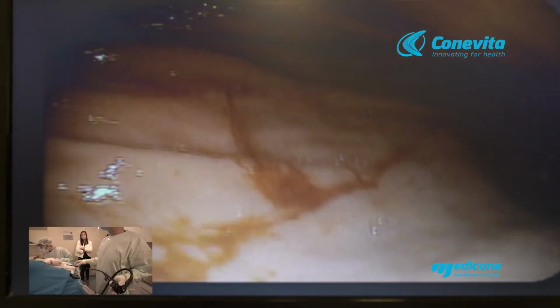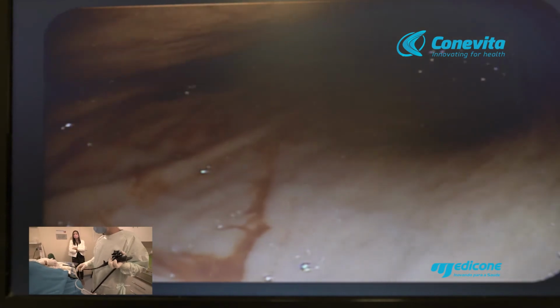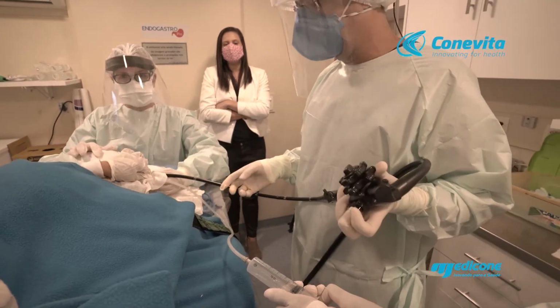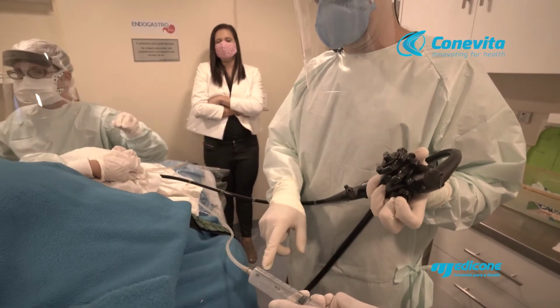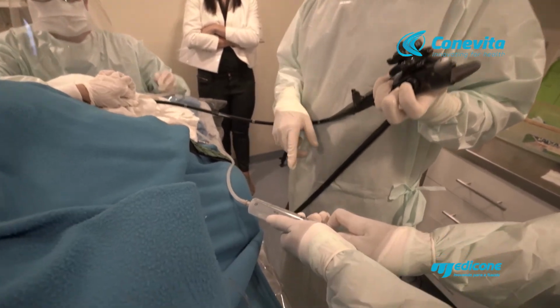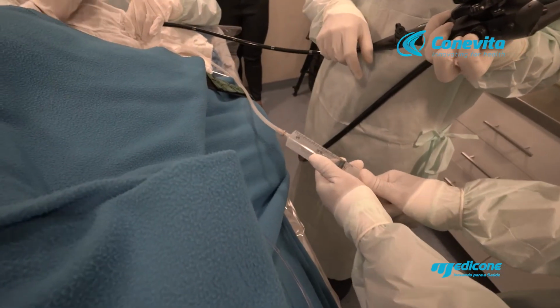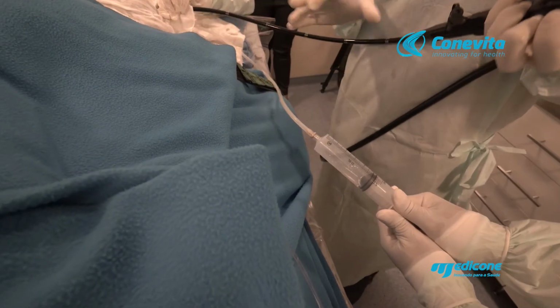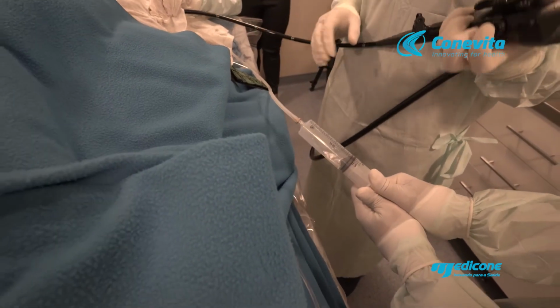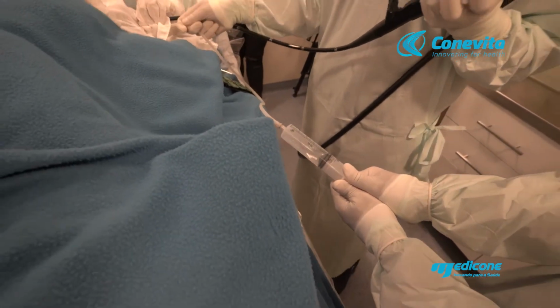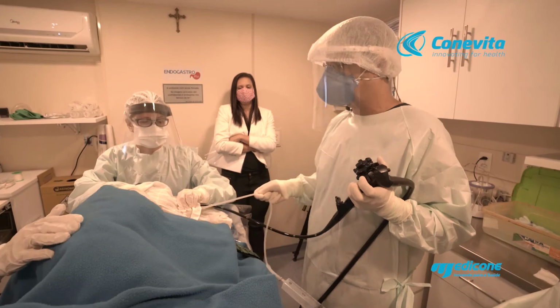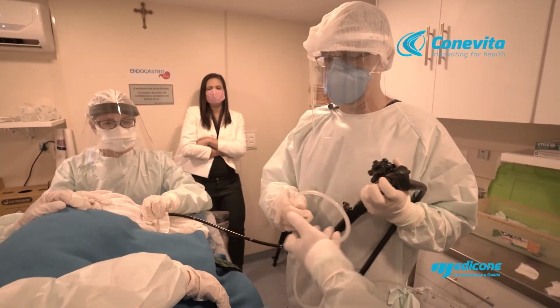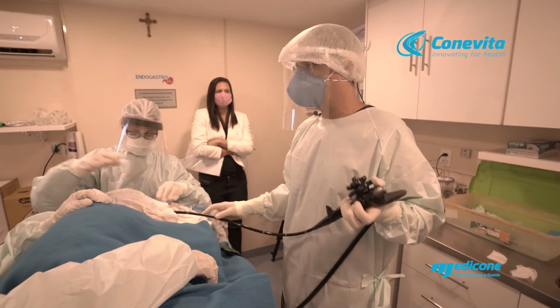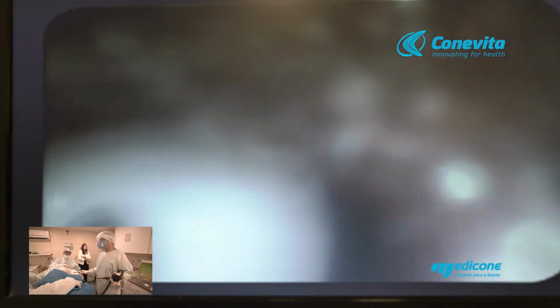Now the balloon is completely inflated, so we have to disconnect the catheter that we use to inflate the balloon from the balloon. It's very important to do a vacuum with the syringe. You can see he's aspirating with the syringe, and we like to hold for 5 seconds, for example, and after that I can pull it out. Okay, so the catheter is completely disconnected, and after that it's important to check the balloon valve. It's what we are doing here.